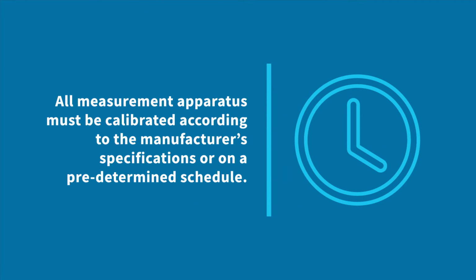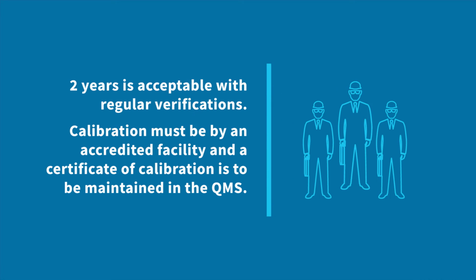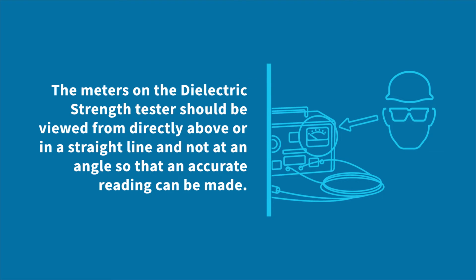All measurement apparatus must be calibrated according to the manufacturer's specifications or on a predetermined schedule. 2 years is acceptable. Calibration must be by an accredited facility, and a certificate of calibration is to be maintained in the QMS. The meters on the dielectric strength tester should be viewed directly above in a straight line and not at an angle so that an accurate reading can be made.